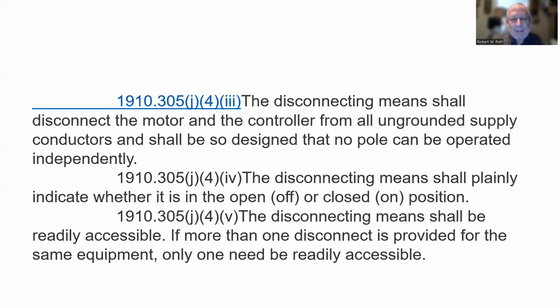Oh well. The disconnecting means shall disconnect the motor and the controller from all ungrounded supply conductors and shall be so designed that no pole can be operated independently. The disconnecting means shall plainly indicate whether in the open or off position. The disconnecting means shall be readily accessible. If more than one disconnect is provided for the same equipment, only one need be readily accessible. So that's your typical pull down. You're on the wall on the box. You pull it down. It's 220 and three phase. It's got three fuses coming down. That's one switch pulls them all down. That's what it's supposed to do.